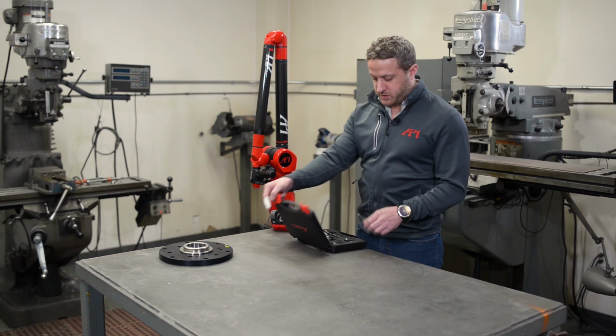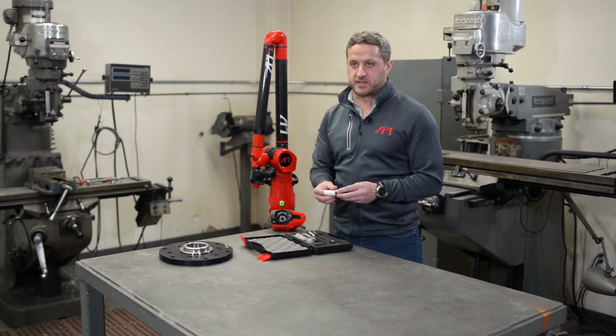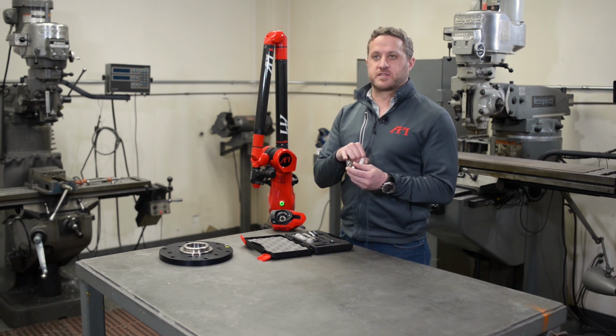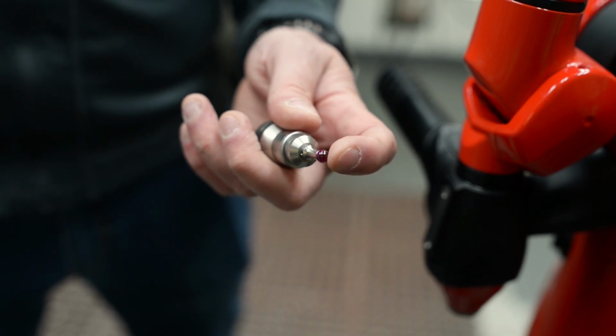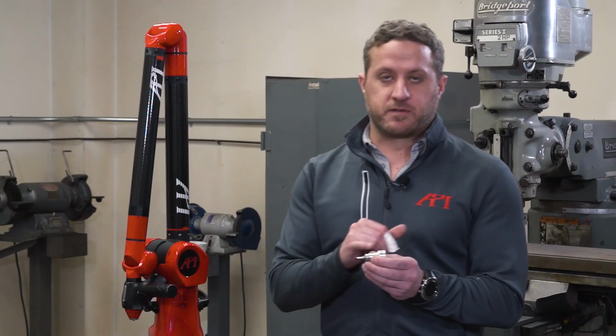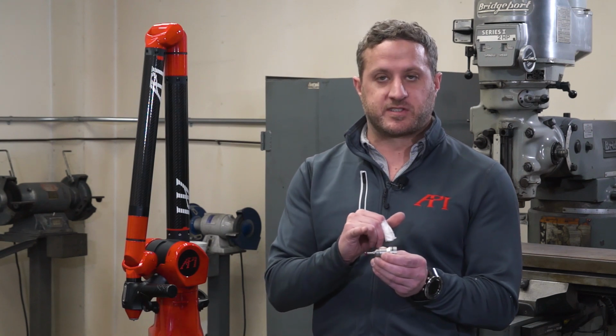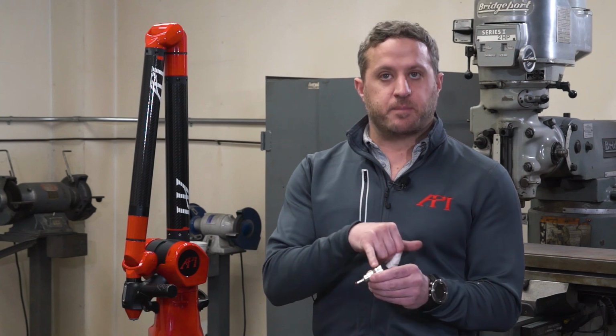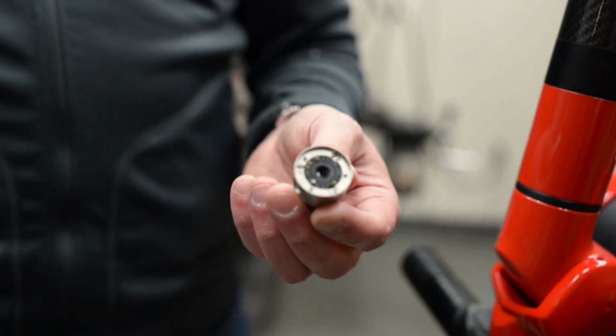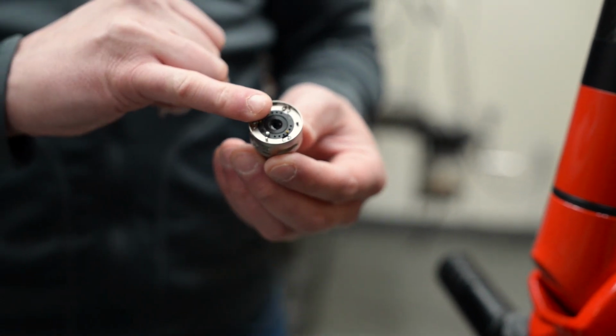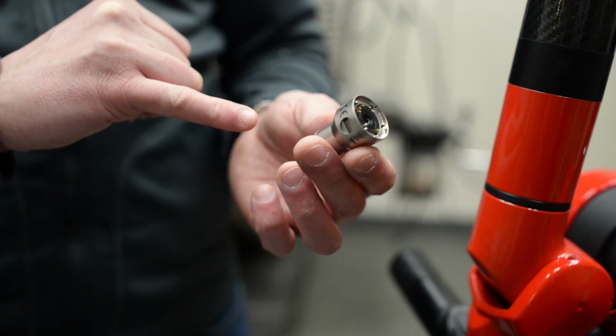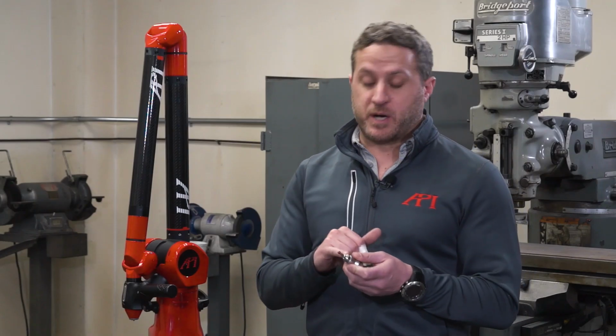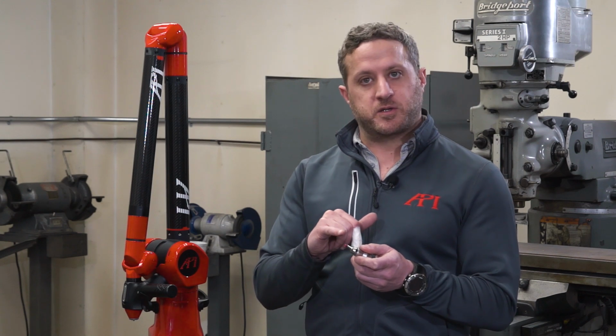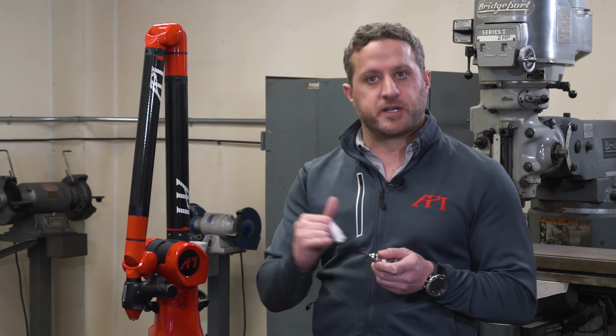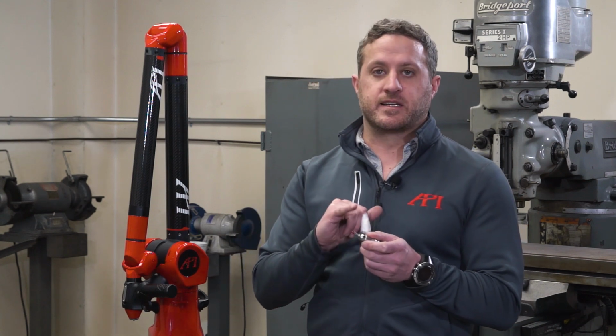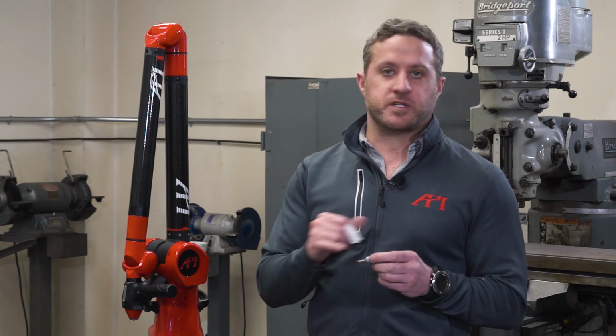Inside the kit, I am going to pull out the probe that comes with it. This is a standard kit where it includes a 6mm ruby tip. The nice part about these ruby tips is that it's modular for the whole base attachment. There are 3 components to it: the actual tip, a spacer, and the base. This base has data information inside of it that will carry your calibration of that probe no matter what computer you go to. It's all stored in the probe. The nice part about it being modular too is that if you want to swap out the probe tip with a longer one or a different material, it's as easy as just buying the tip portion of it instead of purchasing a whole new probe assembly.